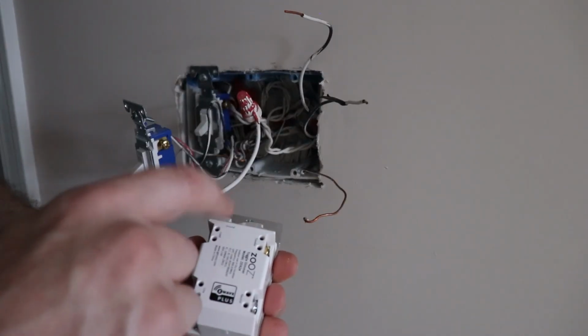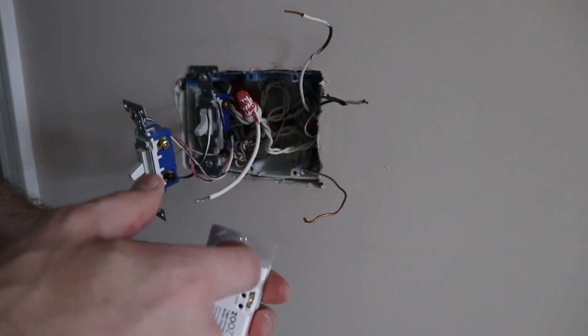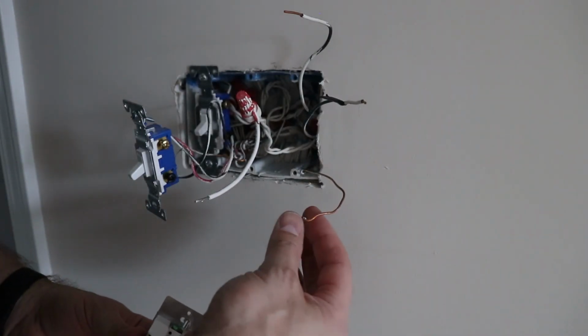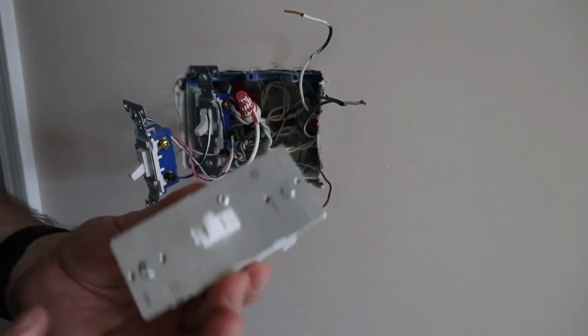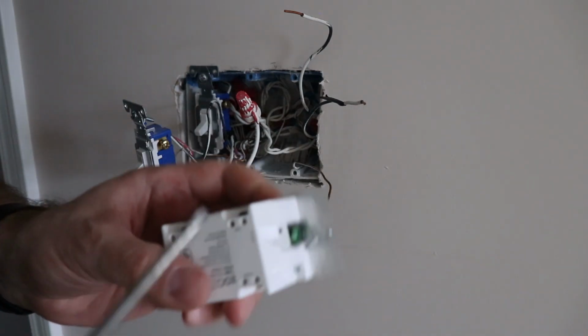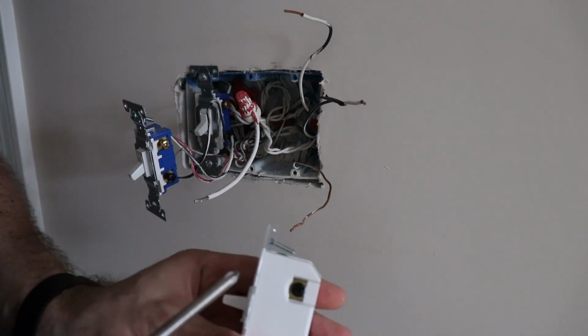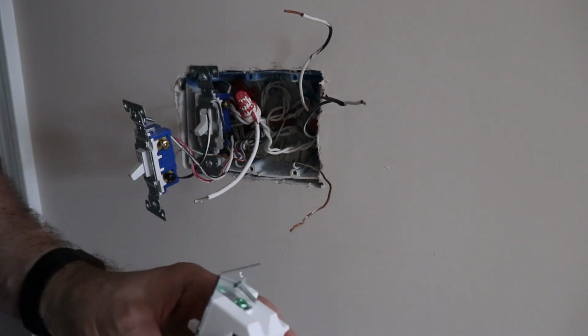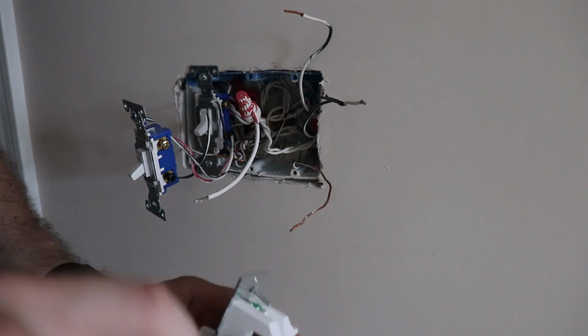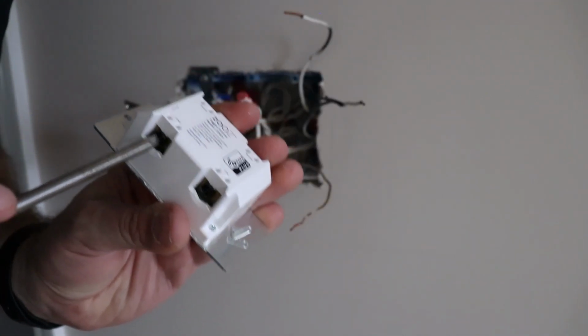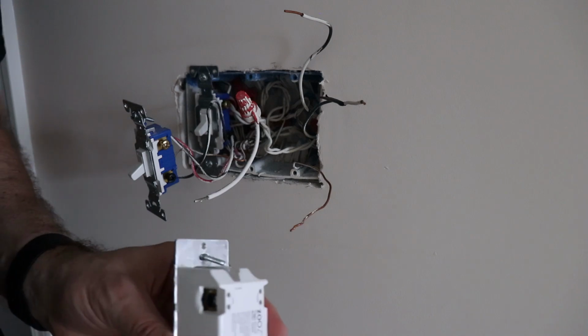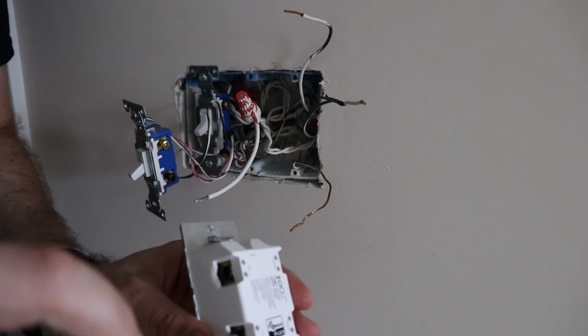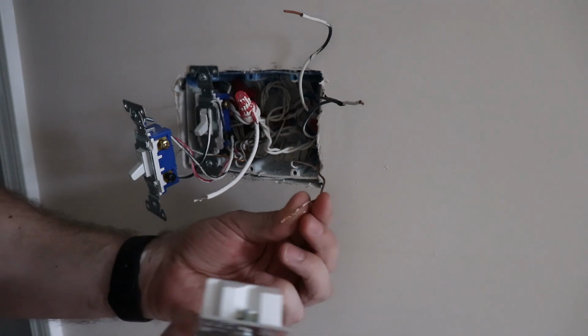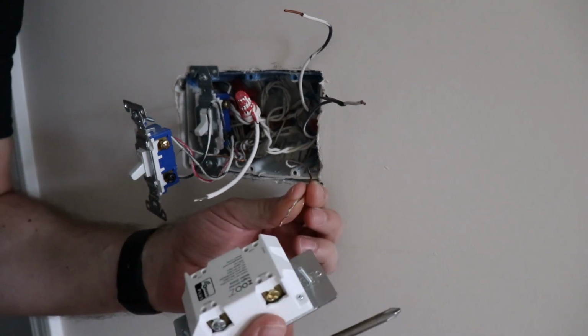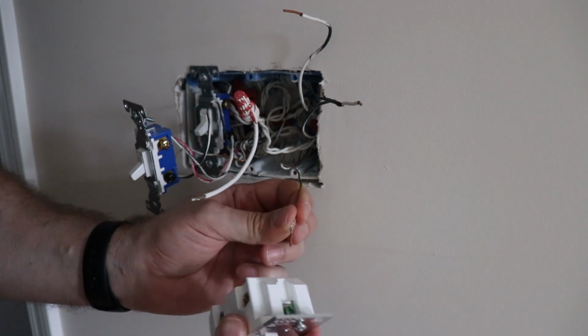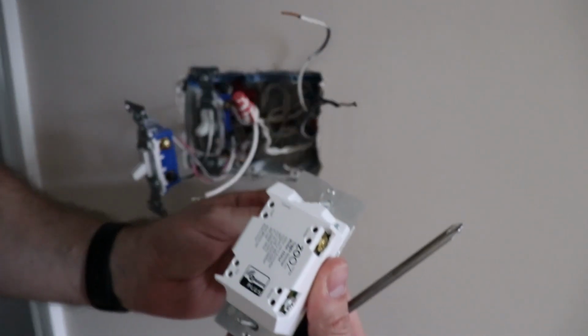This ground wire is going to have to go in this slot here, so I'm going to have to straighten out this ground wire. Now, it's very, very important that you do not unscrew these screws too far. If you do, there is a little plate on the inside that will get separated from the screw, and it will take you hours to get it back. So we have them all loosened a little bit, and now we're just gonna stick them in the holes. So our bare wire is going to go into our ground in the top of the switch.